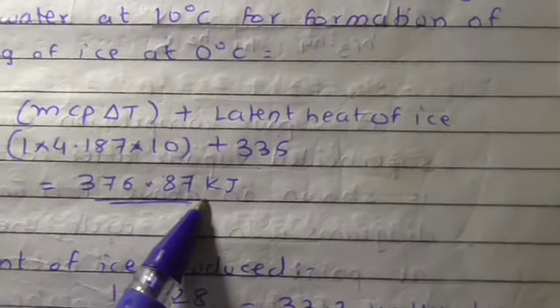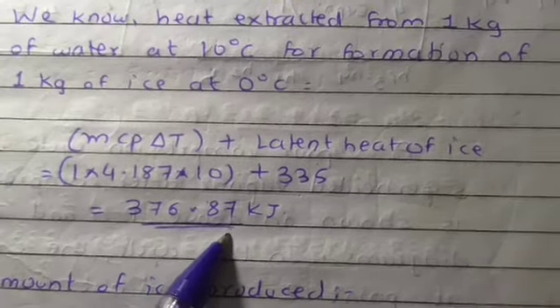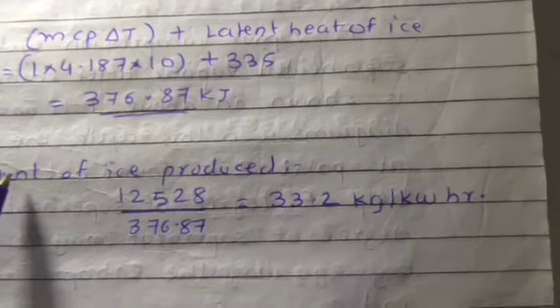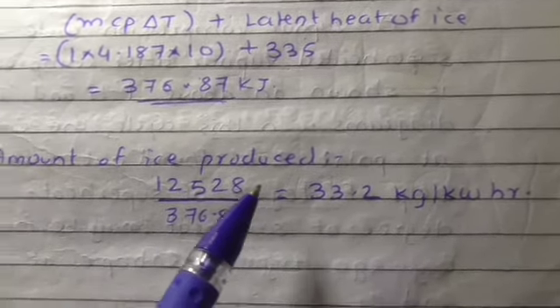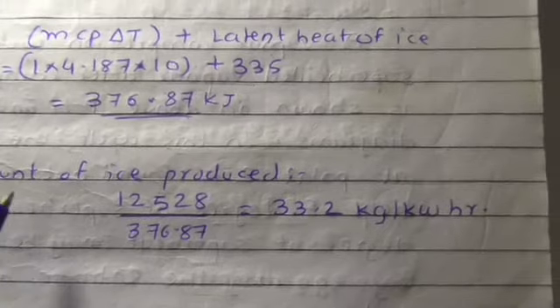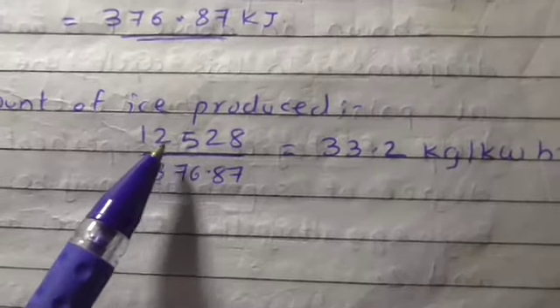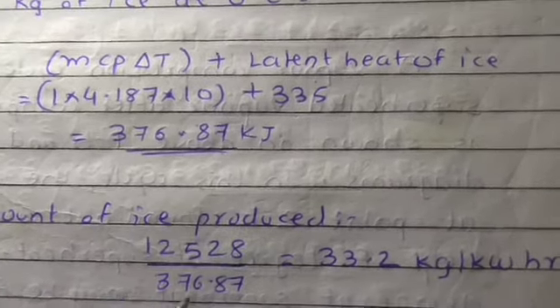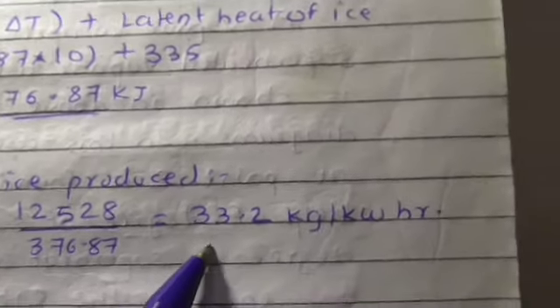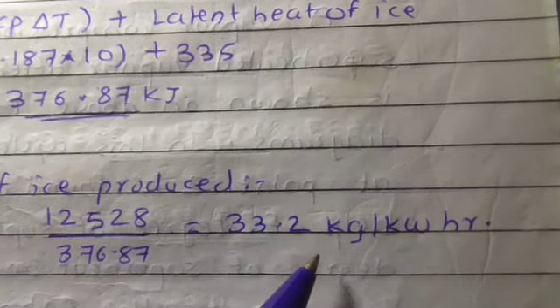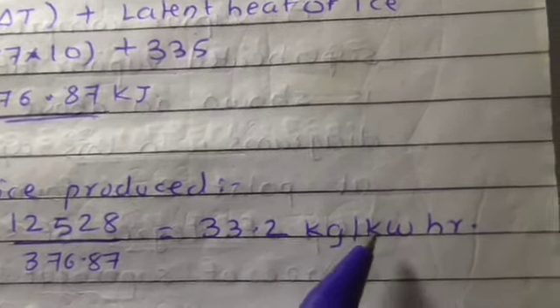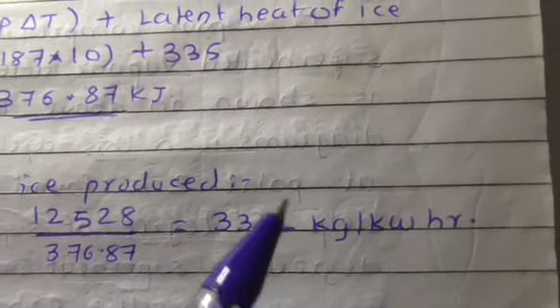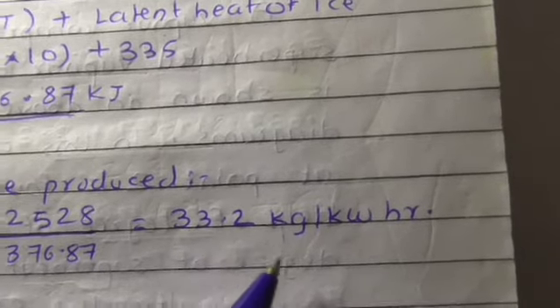Now we have to find the last point: amount of ice produced, how much kilogram per kilowatt hour. The amount of ice produced is 12,528 divided by 376.87 kilojoules, and we get 33.2 kilograms per kilowatt hour. The amount of ice produced is 33.2 kilograms per kilowatt hour.